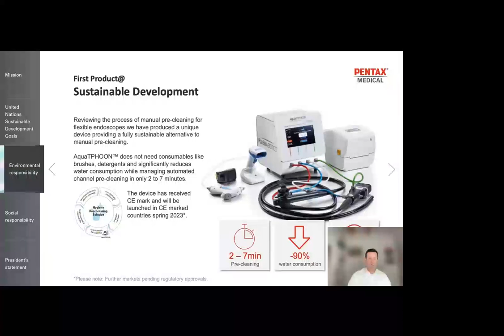Now, this new device uses new smart technology, air and water, in order to clean all the endoscope channels, all of them, before you put them into the washer and disinfector. And it really only takes 2 to 7 minutes. So it's a reduction in time. It uses more than 90% less water than the traditional process. No brushes and no chemicals. And that really is, you could say, a revolution of this process by rethinking what can be done, but also looking into how we can address the sustainability component moving forward. So this product really can reduce waste to a minimum. Against the existing cleaning process, you reduce the waste by more than 99% and really provide significant differentiation.